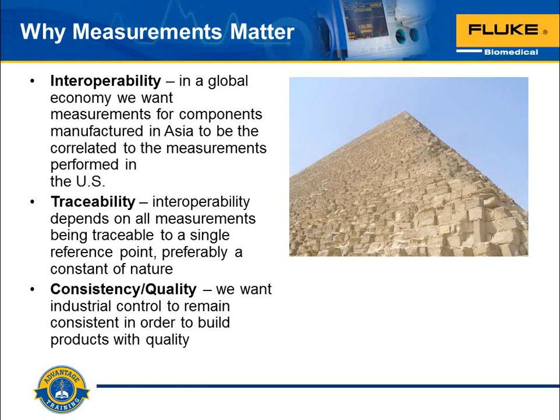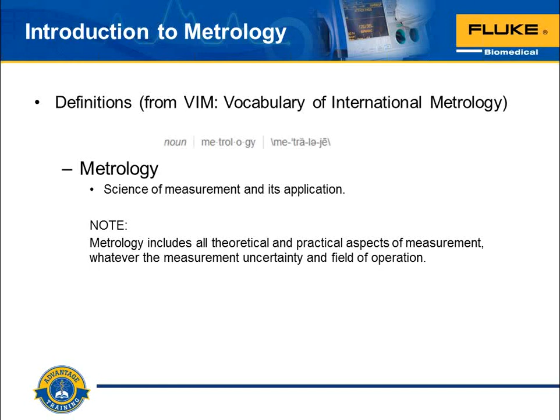Well, let's talk a little bit about some of the definitions of metrology. The term metrology itself, we already talked about a little bit. Metrology is the science of measurement and its application. The measurement that we're talking about is the process of experimentally obtaining one or more quantity values that can be reasonably attributed to a quantity. So when we make a measurement for electrical safety, electrical leakage current, or ground wire resistance, or protective earth resistance, we want that measurement to be reasonably attributed to the exact quantity that we're trying to measure, an ohm or an ampere or a microampere.